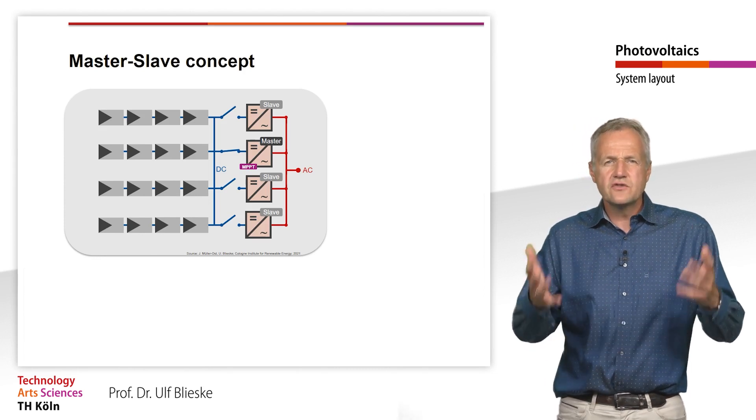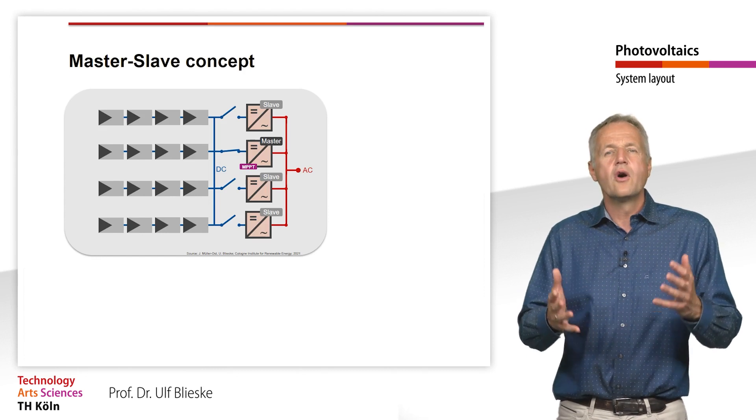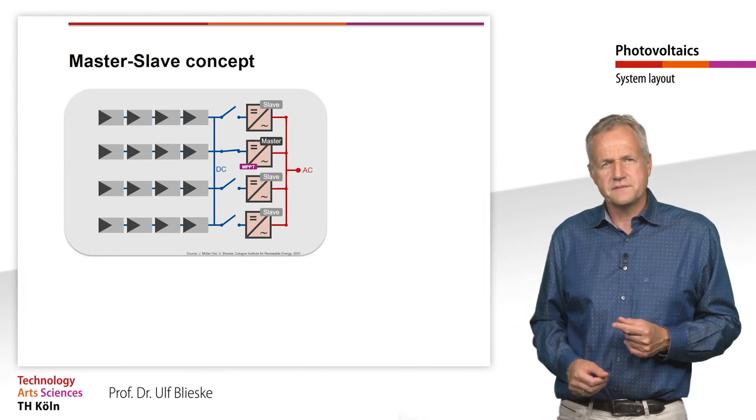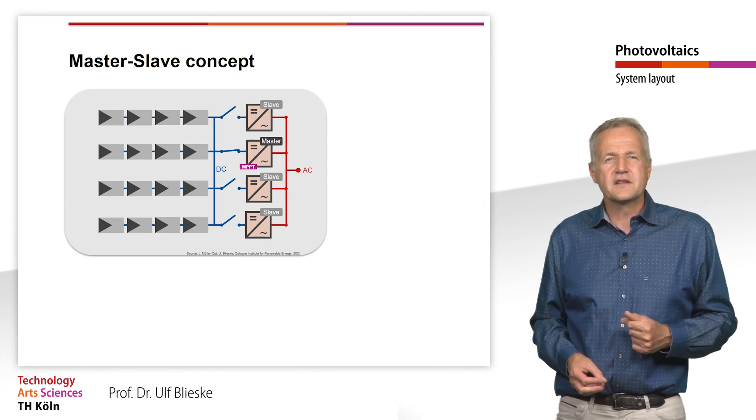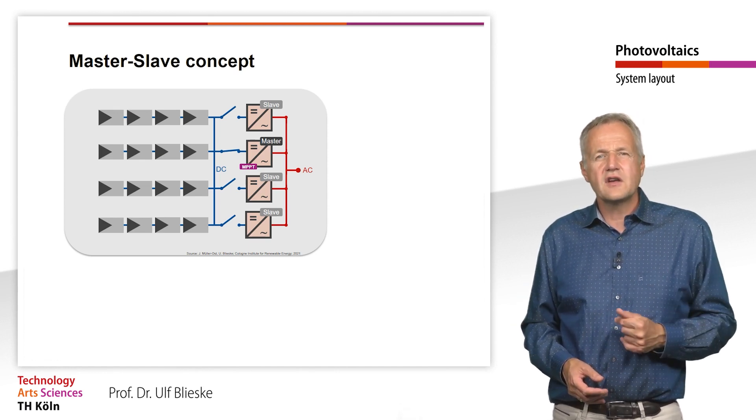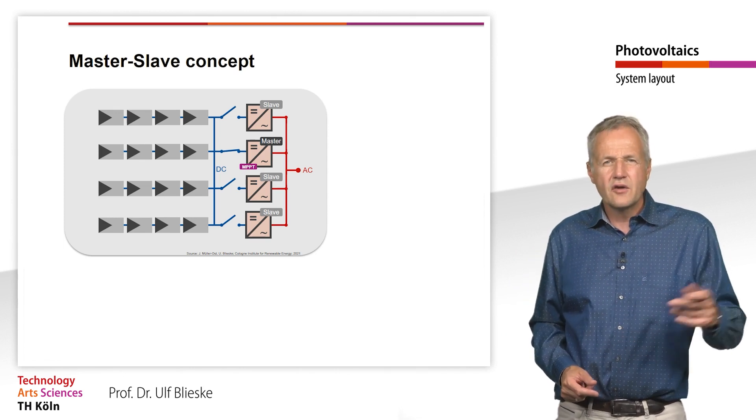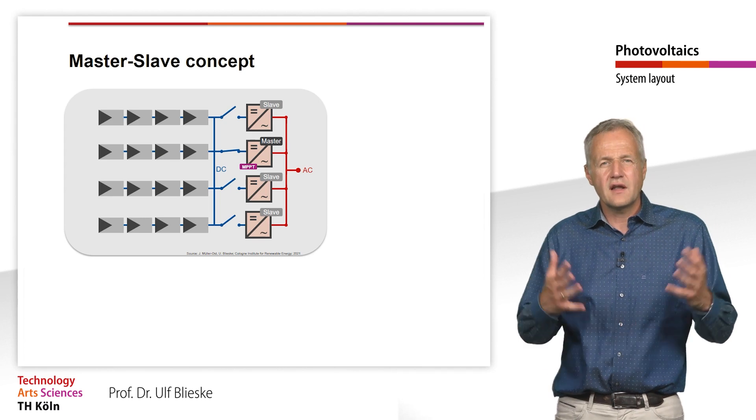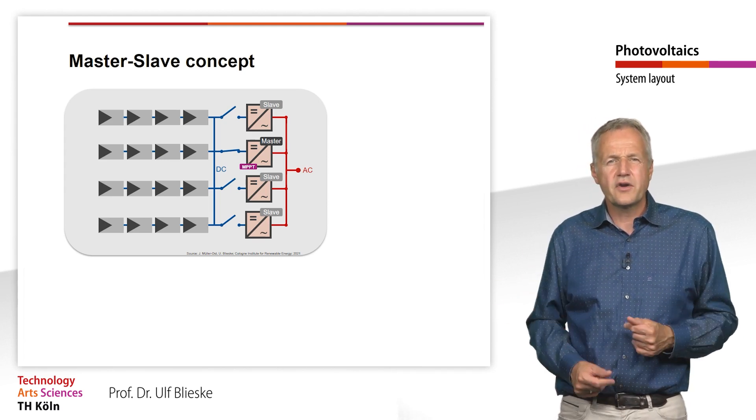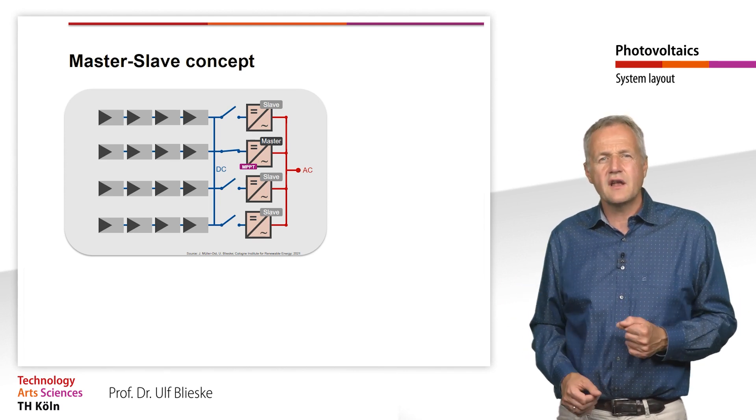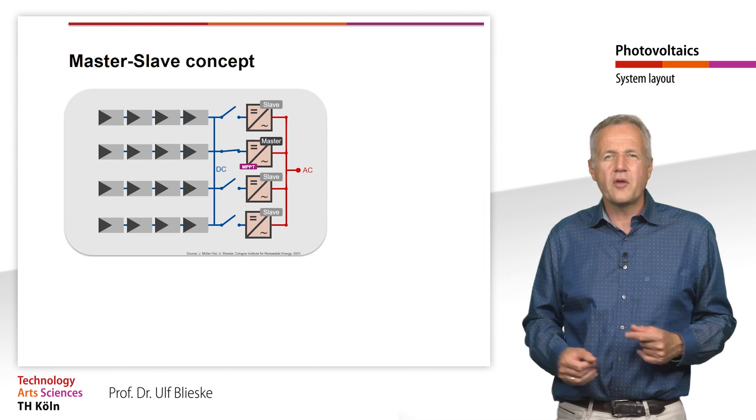Finally, I would like to introduce you to a concept that is used especially in countries with low or alternating irradiation. This system concept is based on the fact that the efficiency of an inverter decreases in the lower partial load range. We had a closer look at this in the last teaching unit. In many PV systems, however, it is precisely in this power range that a large part of the energy is generated. To counter this problem, the so-called master-slave concept is used as an alternative to the central inverter.